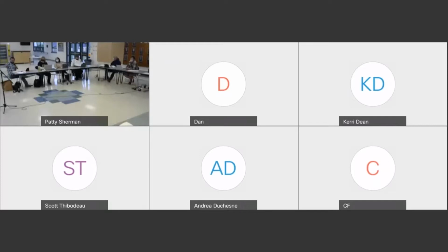John, please jump in and correct me if I misstate anything. That is correct on a lot of these items. There are a few things that we focused on, like the fire alarm, which was grossly outdated and underserving the building. I think we're 3 years or so from that now. Josh was able to get that to a modern addressable fire alarm system that could be expanded if the building is expanded. So there are some critical life safety things that you can do whether or not you expand the building, but with electrical and things like that, you get by. So we can address it all at once.